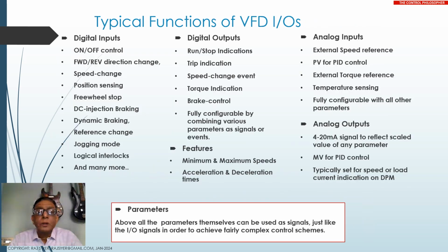So, okay, as discussed in the previous slide, there are a number of functions that can be assigned to each input or output signal of the VFD. For example, for digital inputs you can have values assigned such as on-off control, forward, reverse, speed change, position sensing, free wheel stop, DC injection braking, jogging. You can use them for logical interlocks and many things. Some 10-20 functions are easily had in any drive.